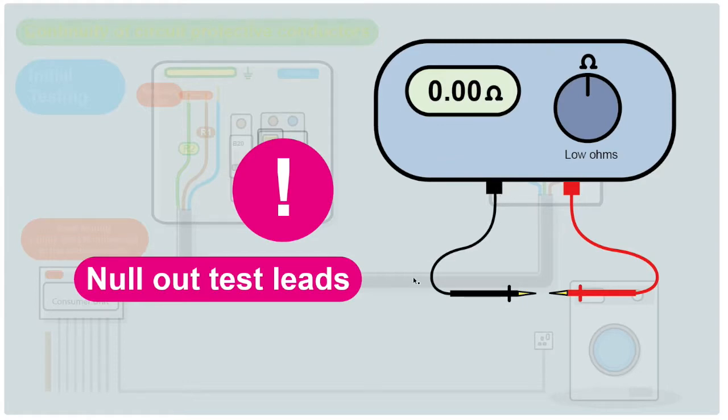When you put the probes together and press a button it'll null out the reading. You'll get a reading of 0.00 on your display, and any reading that you do get when you're doing your testing is purely the circuit you are testing and the leads are not adding to that resistance.